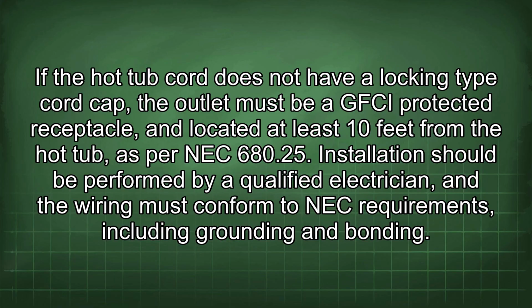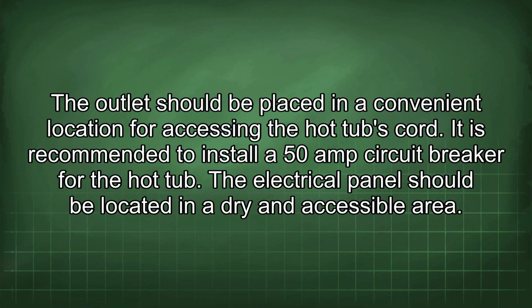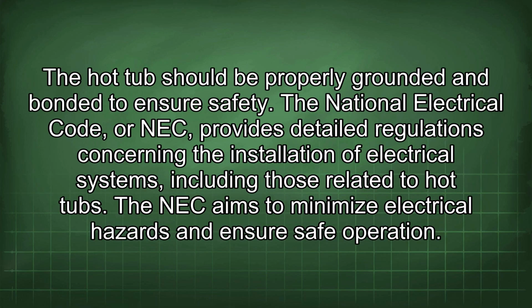680.25. Installation should be performed by a qualified electrician, and the wiring must conform to NEC requirements, including grounding and bonding. The outlet should be placed in a convenient location for accessing the hot tub's cord. It is recommended to install a 50-amp circuit breaker for the hot tub. The electrical panel should be located in a dry and accessible area. The hot tub should be properly grounded and bonded to ensure safety.